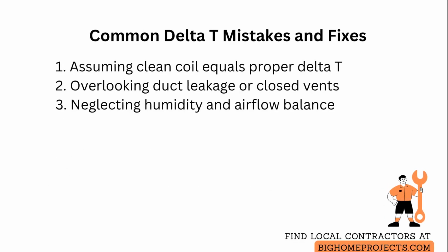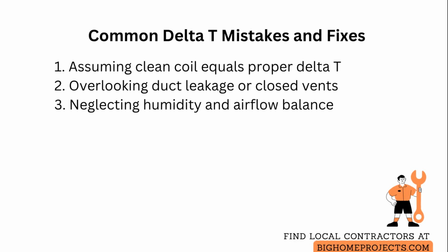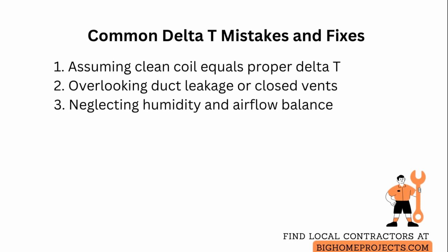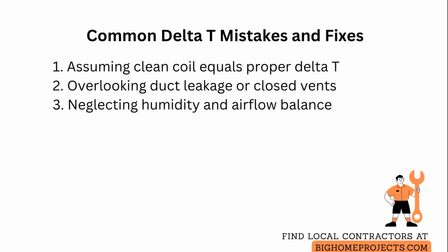Common mistakes include assuming a clean coil guarantees proper delta T, which misses low refrigerant charge. The fix is to validate pressures and charge by weight against specifications.